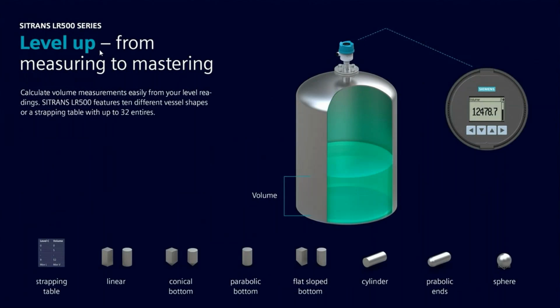The volume of the material within the tank or silo can also be calculated. This is an enhancement from the previous version. So the 500 series includes 10 vessel geometries or a strapping table with up to 32 points to relate volume from level. We have a lot of these conversations with customers for inventory control where they might want to do a strapping table, but sometimes they're doing that in the PLC. Just know that the software is built into these new transmitters so that you can actually do this via the transmitter.